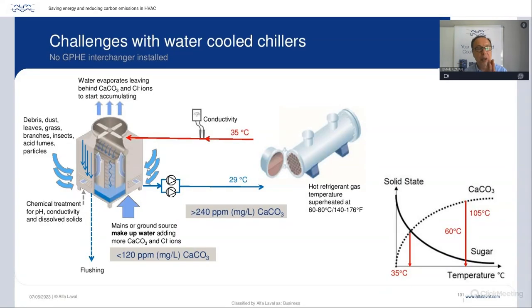Now, the problem with cooling towers, really, friends, is that cooling towers are never well maintained, and they have a buildup of calcium carbonate. As the water evaporates, as you see here, the calcium carbonate and chloride ions actually accumulate. It's like a mineral deposit box. The only way to remove this is really to flush the cooling tower regularly. If we don't, the calcium carbonate goes with the cooling tower water into the condenser, and on a hot surface, it precipitates, comes out of solution, and sticks itself onto the hottest surfaces, and that is typically the condenser.